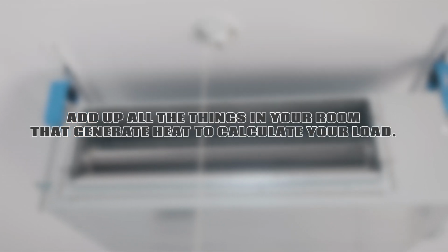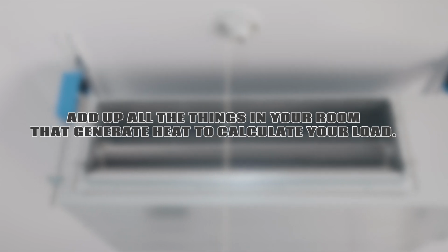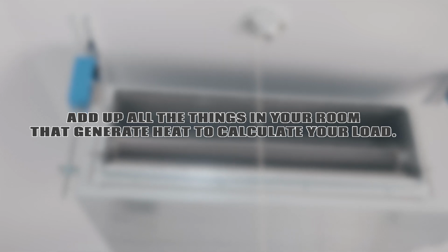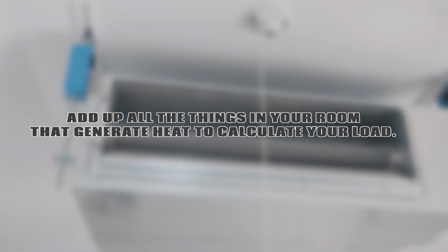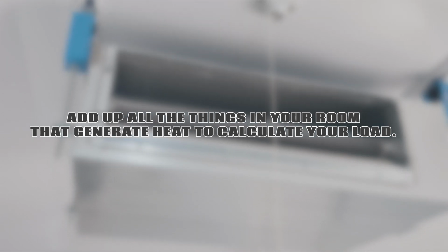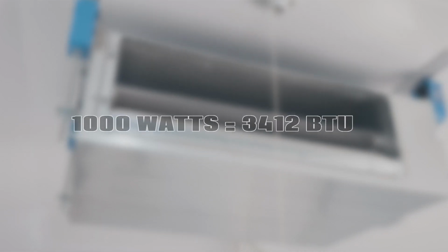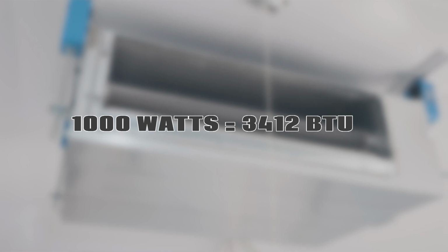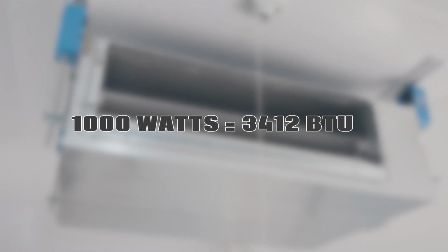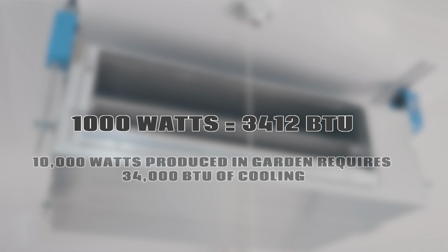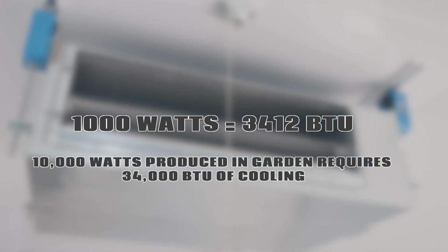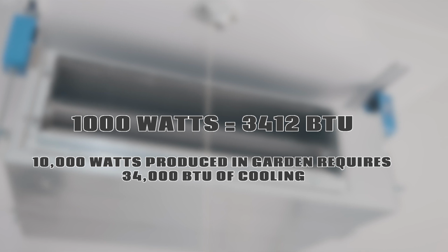When sizing and coming up with your plan for your garden, it's really important to assess how much load we have. The simplest way is to sit down, take your fan count, all your oscillating fans, your dehumidifier output rating, your lighting output rating, put that all together and then convert that from wattage to BTUs. For every 1,000 watts, it requires 3,412 BTUs to cool it. So if I've got 10,000 watts of light and energy being made in my garden, I need 34,000 BTUs.